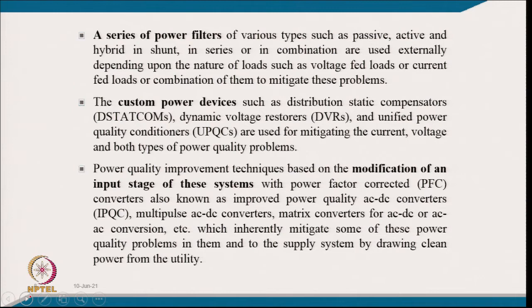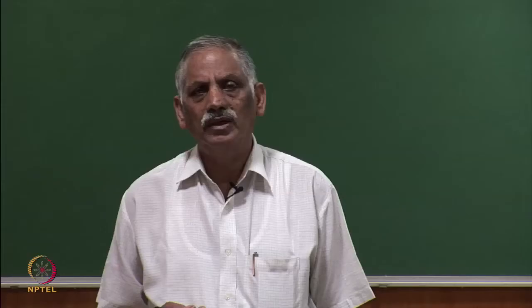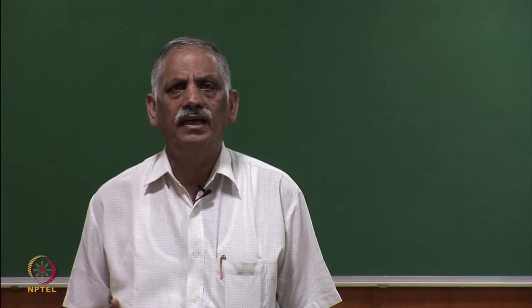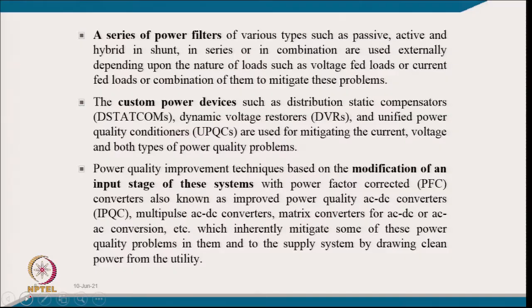A voltage-fed load is, for example, a diode rectifier with a capacitor at the DC link to produce constant DC link voltage. A current-fed load is typically a thyristorized power controller — an AC to DC converter with thyristors and a large inductance on the DC side — feeding either a current source inverter for AC motor drive, a DC motor drive, or field excitation of an alternator.